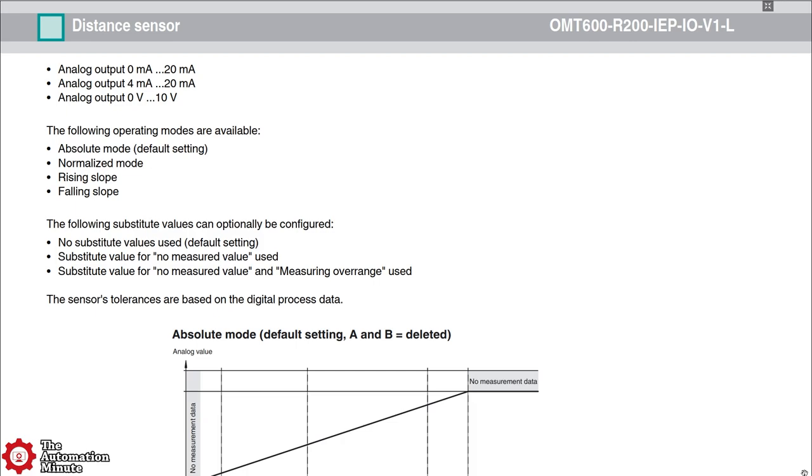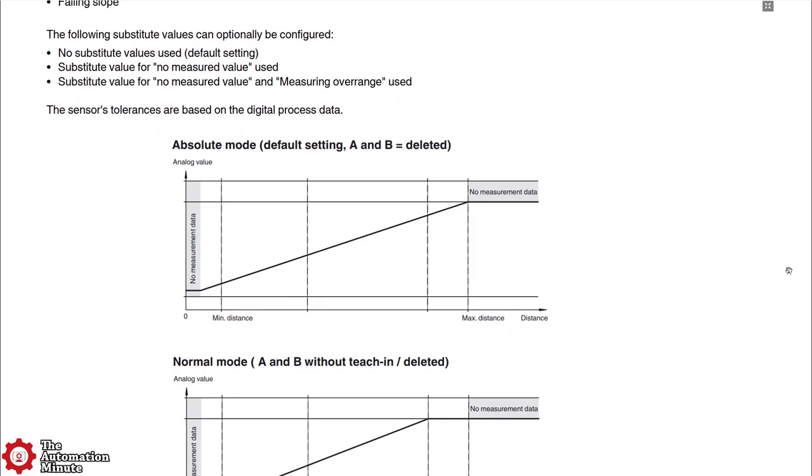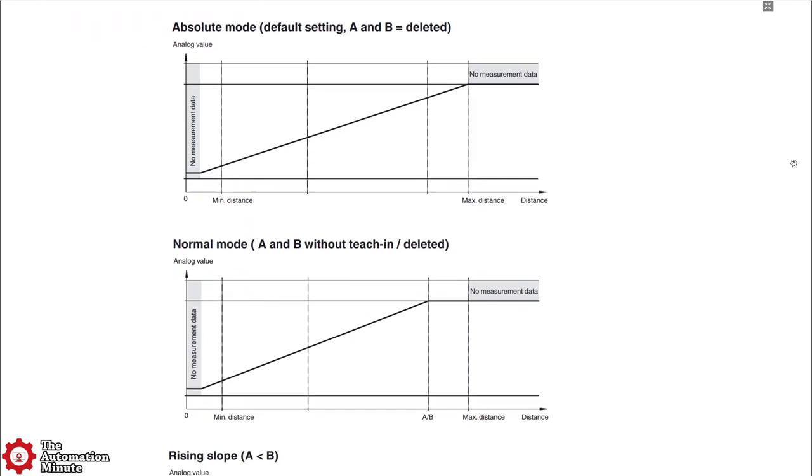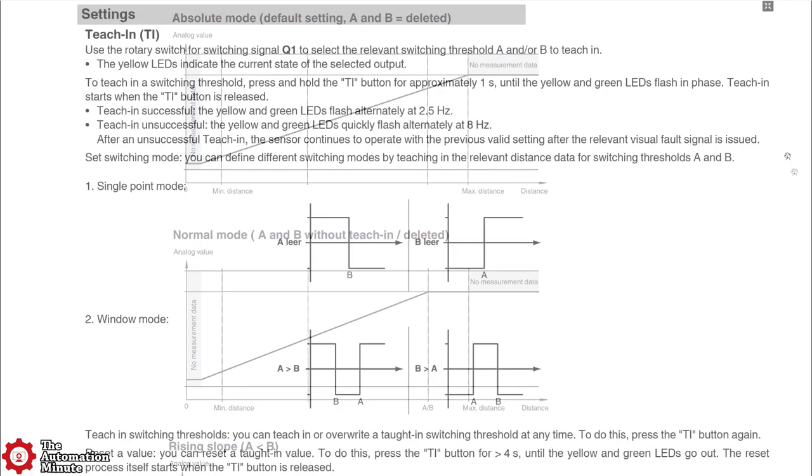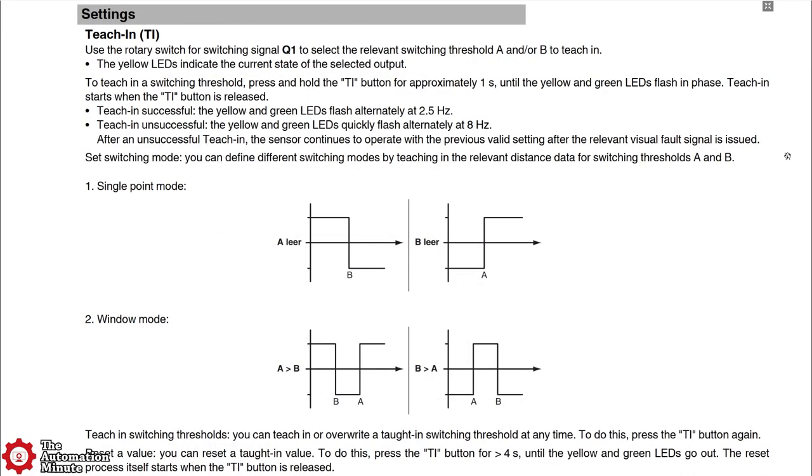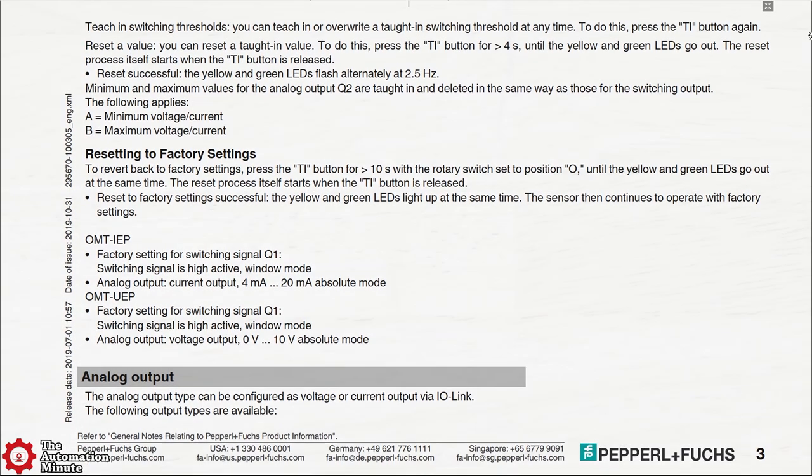In addition to its IO-Link capabilities, there is a mode switch on the top of the unit that can be used to switch between the absolute, normalized, rising slope and falling slope modes. There's also a teach-in switch to set the A and B thresholds for both the Q1 discrete and Q2 analog outputs.